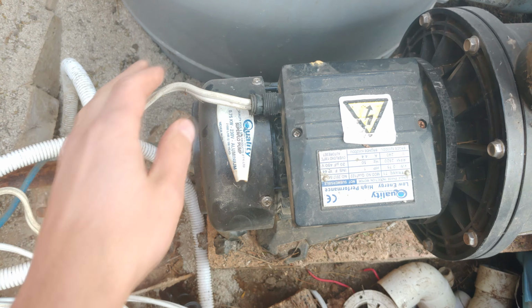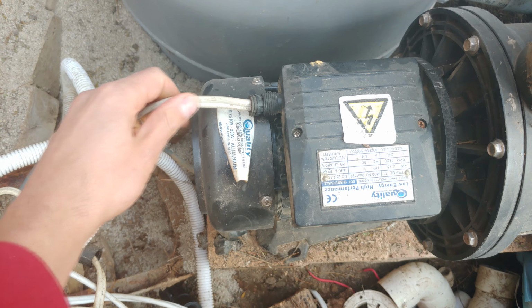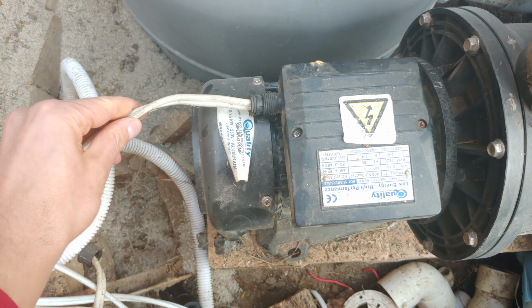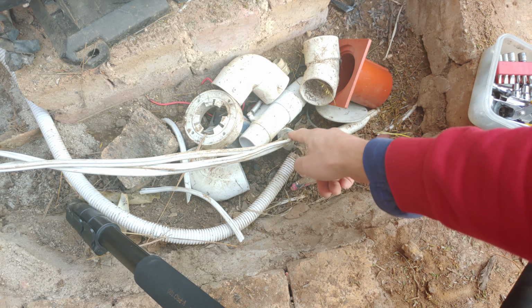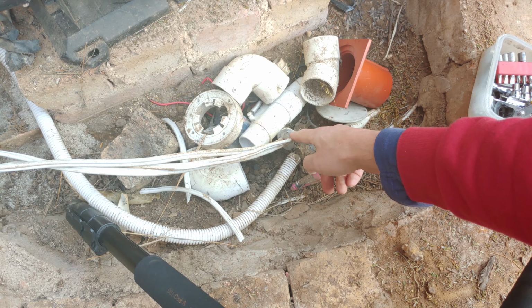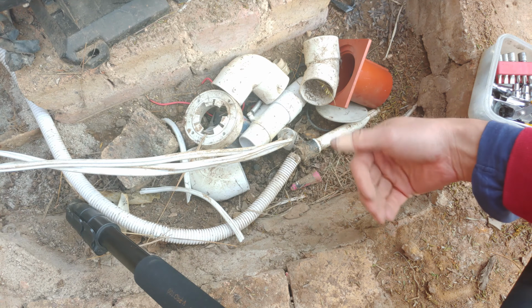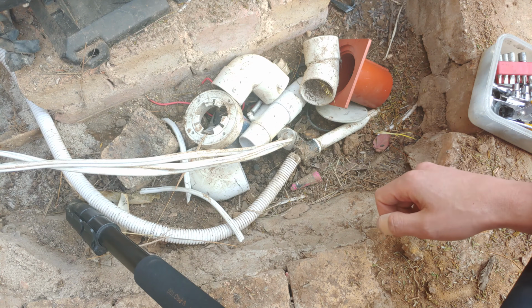If this is a new installation, please use flexible cable. As you can see, this is a solid core cable and it should have been flexible. Okay, the cable is then coming here and it's going in the conduit into the ground, and it comes out the other side where the DB board is.